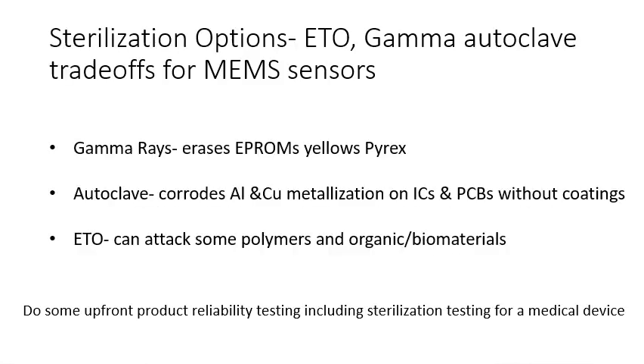Sterilization. You wouldn't think of this as a barrier, but obviously to sterilize something, you're able to kill bacteria and viruses. Some of those techniques can damage electronics or MEMS devices. Gamma rays, very common. It'll erase many EPROMs. It'll actually turn Pyrex yellow. Autoclave, that's just hot high pressure steam, that'll corrode aluminum and copper metallization on ICs, circuit boards.